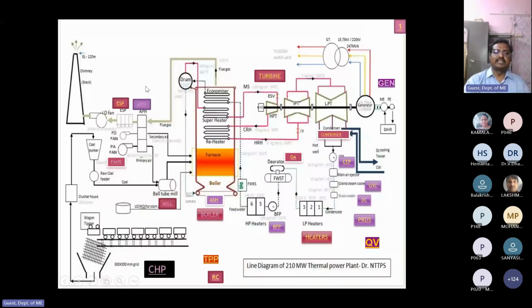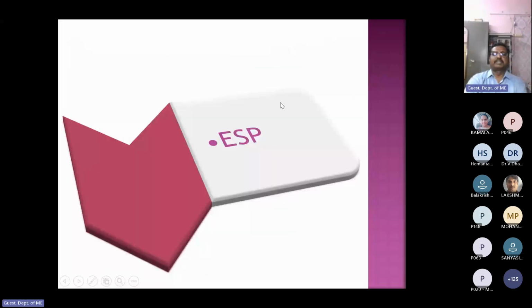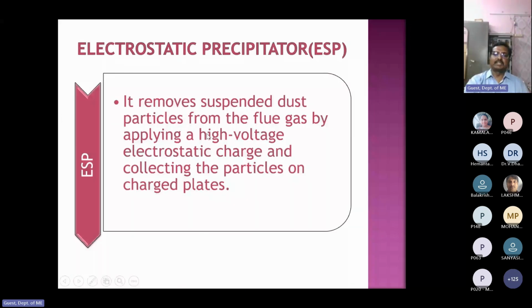Next one is the ESP. Going one by one. After the air heater, the flue gas goes to the ESP directly. The purpose of the ESP is to remove the ash particles mixed with the flue gases. ESP stands for electrostatic precipitator. It removes the suspended dust particles from the flue gas by applying a high voltage electrostatic charge and collecting the charged particles. So high voltage is generated inside the ESP.